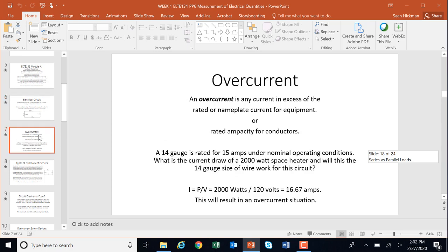An overcurrent is when you have excess current for the rated nameplate of the equipment. Usually you think about your house — you're turning on lights, or turning on a hairdryer or an air conditioner or a stove, electric things. When for some reason that load or the circuit is seeing a current in excess of what it wants, then you've got an overcapacity. What that can do is cause a problem because the conductors, the wires running to that, the wires in the wall of your house, are only designed to handle a limited amount of ampacity or amps. So if you get too much, then you're going to get a fire — they're going to burn up.